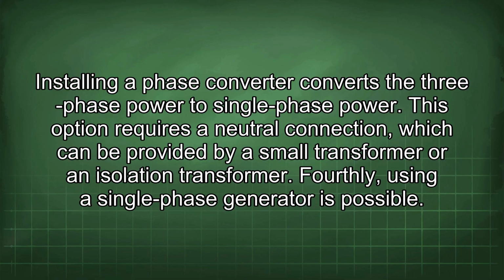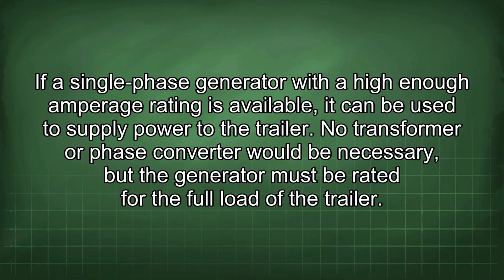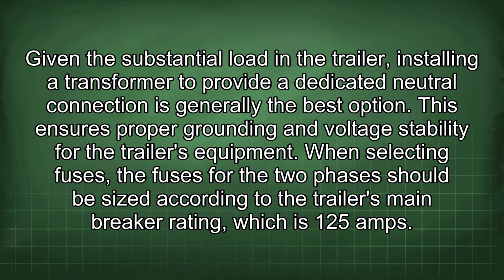Fourthly, using a single-phase generator is possible. If a single-phase generator with a high enough amperage rating is available, it can be used to supply power to the trailer. No transformer or phase converter would be necessary, but the generator must be rated for the full load of the trailer. Given the substantial load in the trailer, installing a transformer to provide a dedicated neutral connection is generally the best option. This ensures proper grounding and voltage stability for the trailer's equipment.